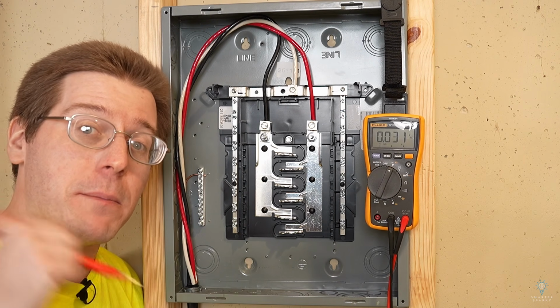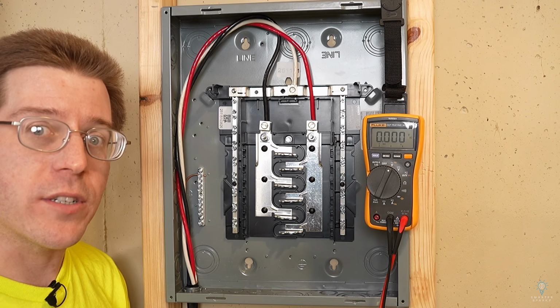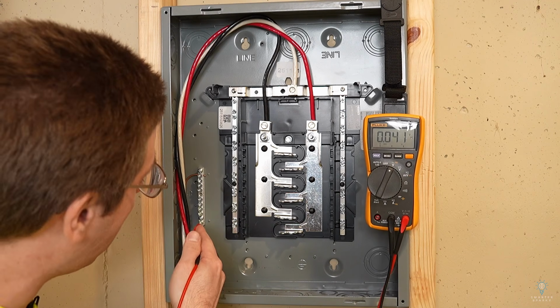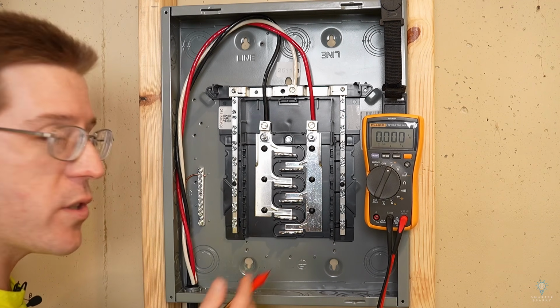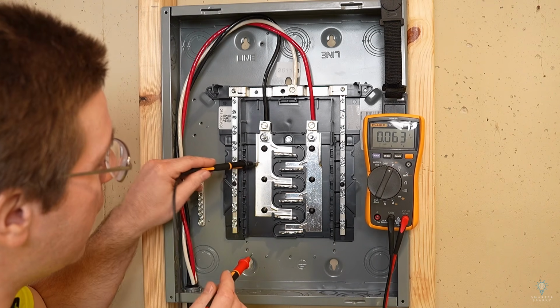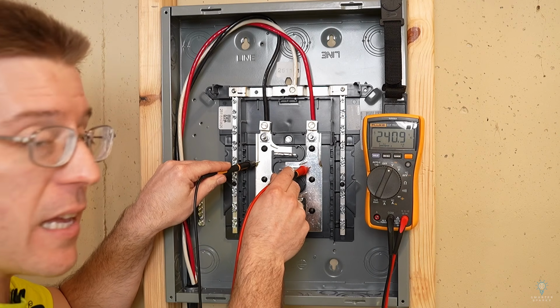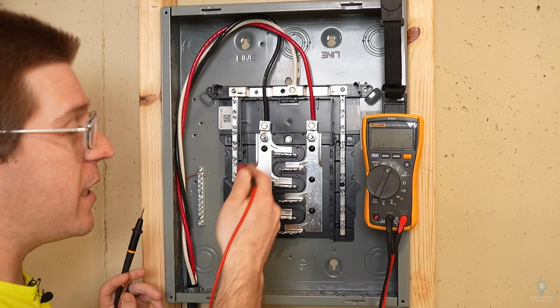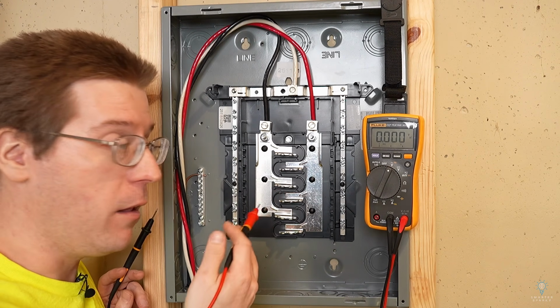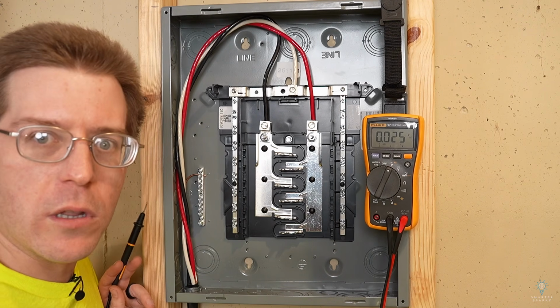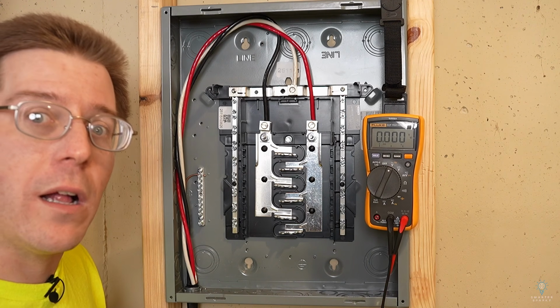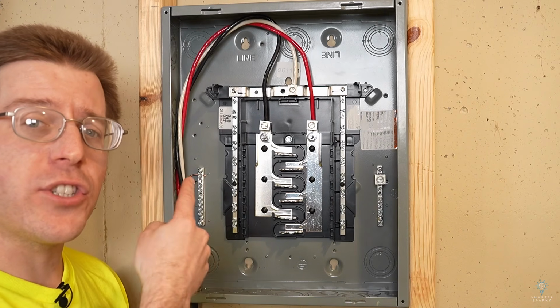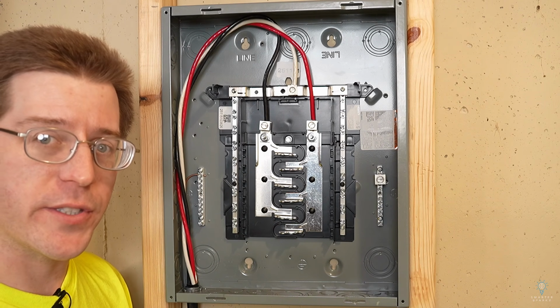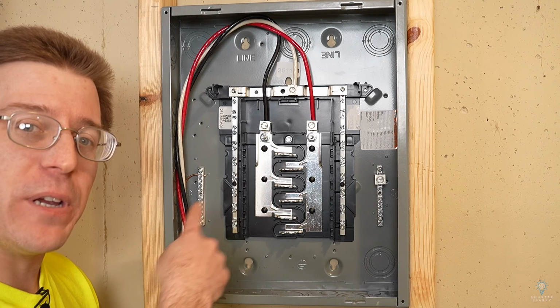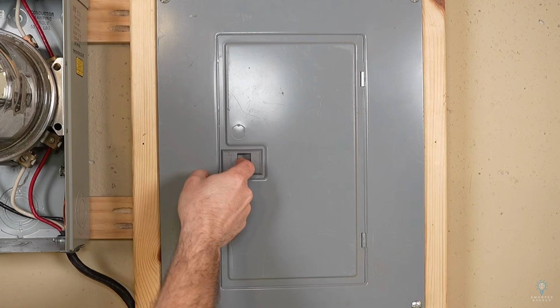So from line to ground, we get 120 volts, because remember, at the main electrical panel, neutral and ground are tied together. But in the sub panel, grounds are separate and neutrals are separate. Of course, if we had a 2-pole breaker connected to both of these bus bars, that's where we could get 240 volts. So we could put a 2-pole breaker in this sub panel and feed a 240 volt load, such as a dryer, a range, a welder receptacle, or an RV plug. So let's shut this panel off and wire a receptacle circuit out of the panel and see how everything actually lands within the panel.